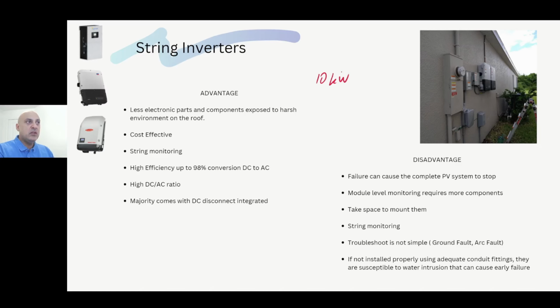So if we have a 10 kilowatt inverter, right? And it also tells you on the DC, the maximum power is 15 kilowatts. So the DC AC ratio is just gonna be, yeah, you guessed it, 1.5. So basically the inverter can handle 50% more than its rated nameplate power output, if you want to call it like that. And you're wondering, okay, but why do I want something like that? Well, it can help you reduce cost in your systems.